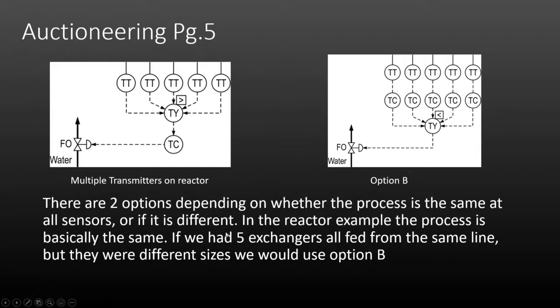The first is the easier, cheaper version with multiple transmitters on the reactor. Option B has multiple different controllers on the reactor, giving much more detailed control. In an exchanger application where all units are fed from the same steam line but are different sizes, you'd use a different controller on each one because they'd have different tuning parameters for each exchanger.